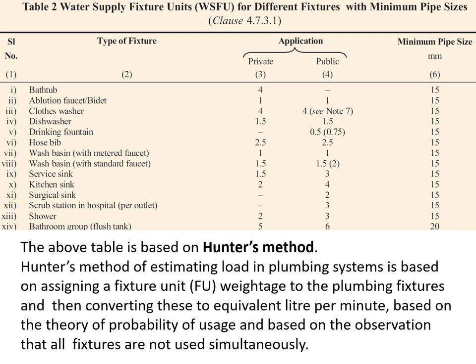National Building Code of India, Part 9, recommends water supply fixture units for different fixtures with minimum pipe sizes through a table. For a bathtub spout, the water supply fixture units are considered 4, and the requirement can be fulfilled by a 15 mm diameter pipe. For an ablution tap, the water supply fixture unit is considered 1. For a clothes washer or washing machine, it is 4. For a dishwasher, it is 1.5. For a kitchen sink, it is 2. For a shower, it is 2, and the minimum pipe size required is 15 mm.